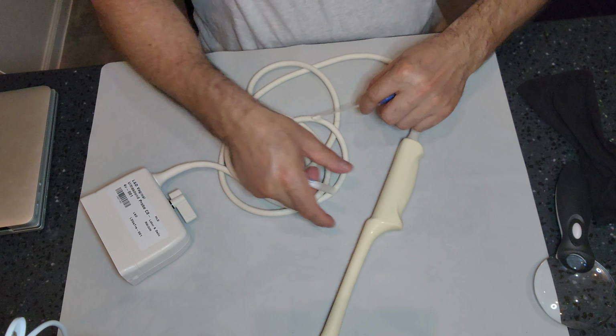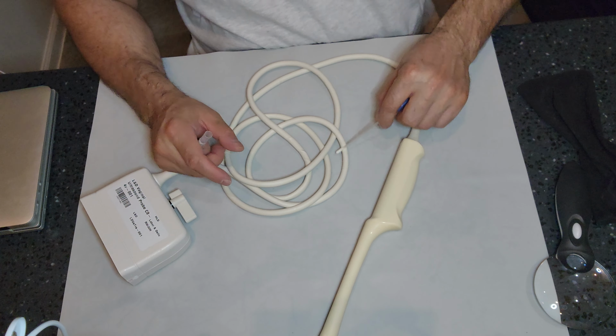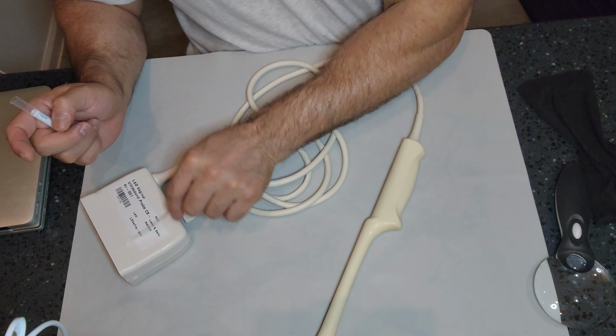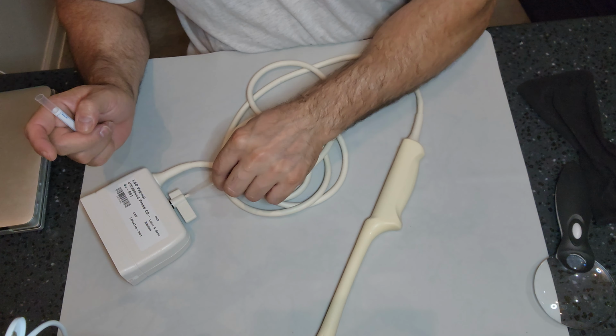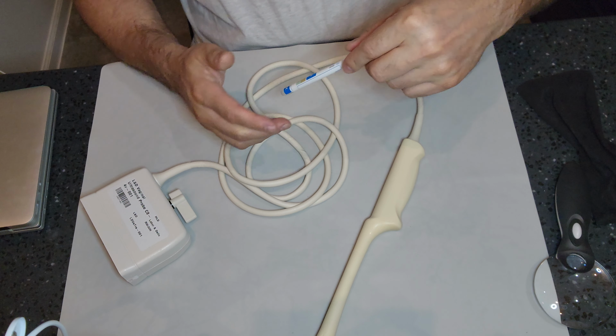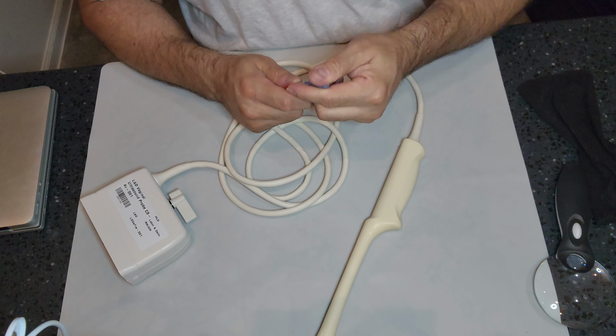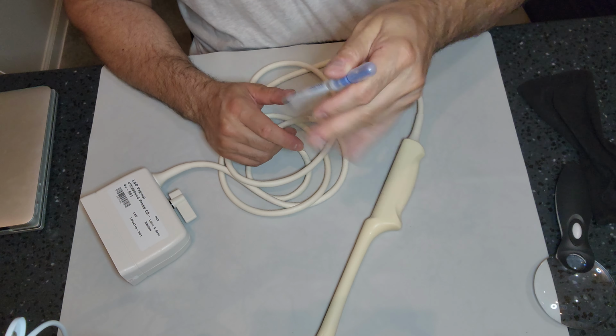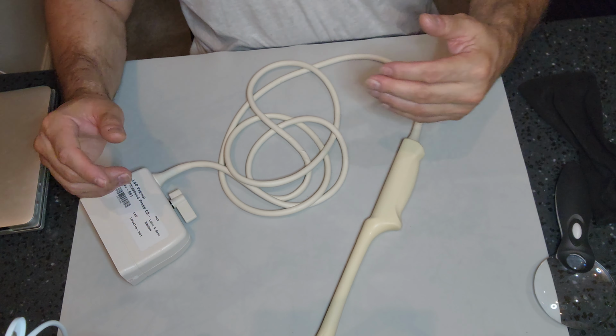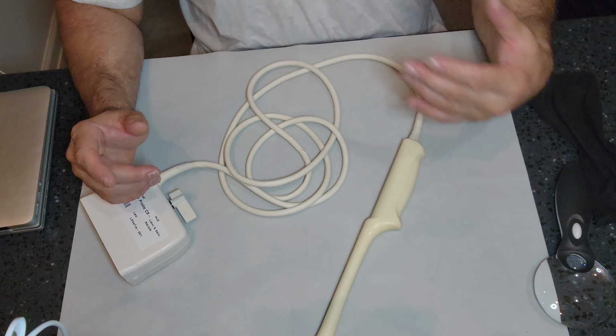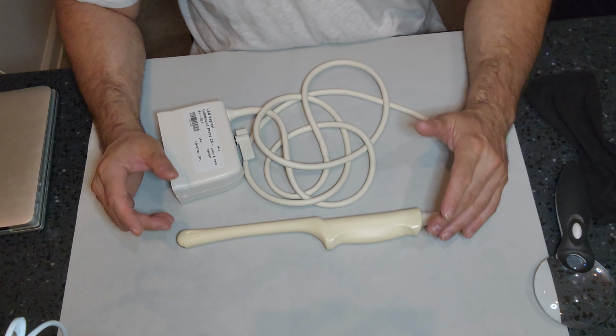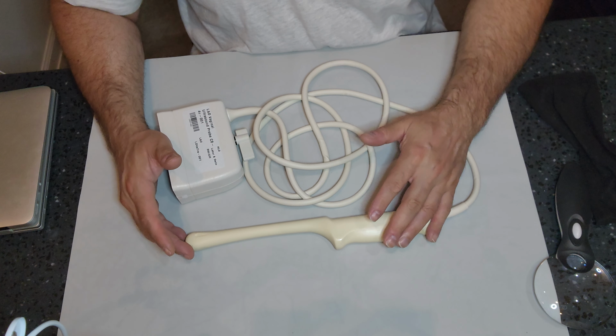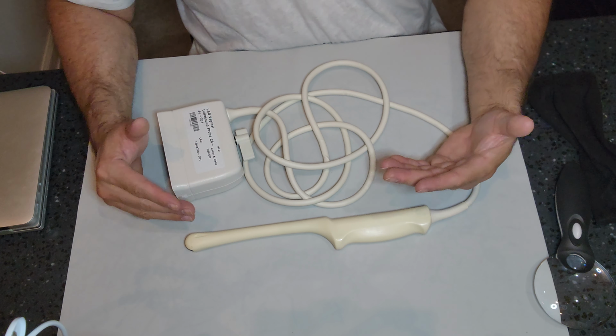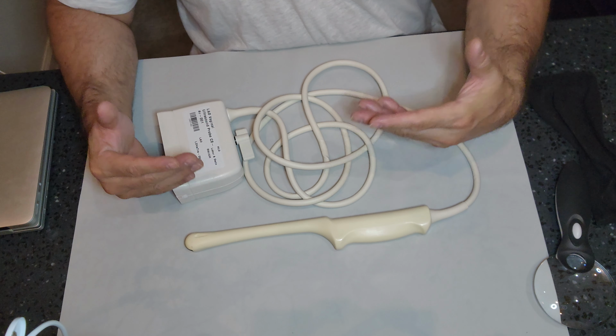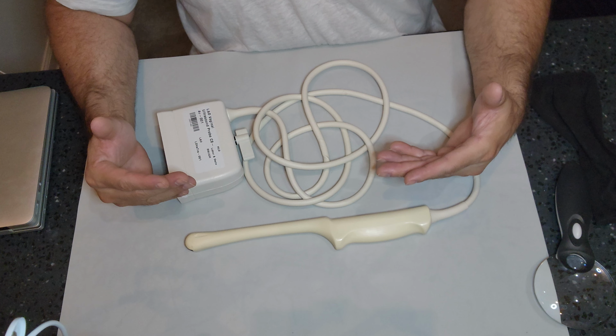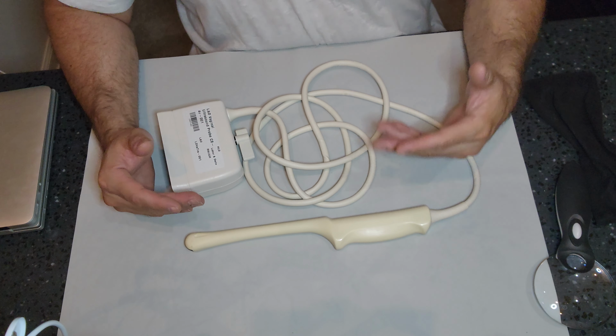How good was your low-level disinfecting? So take multiple spots in there, right? Because if any part of this comes back with a hit, then we know that we didn't do our job correctly. So you want to go ahead and get that soil in there and see what you got. If it came out good, then you can go ahead and go to the final step, which is either high-level disinfecting or sterilization of your probe. And again, guys, whichever process you use, whether it's high-level disinfectant or sterilization, the handling afterwards determines how that item is upkept or maintained before it's used on a patient.